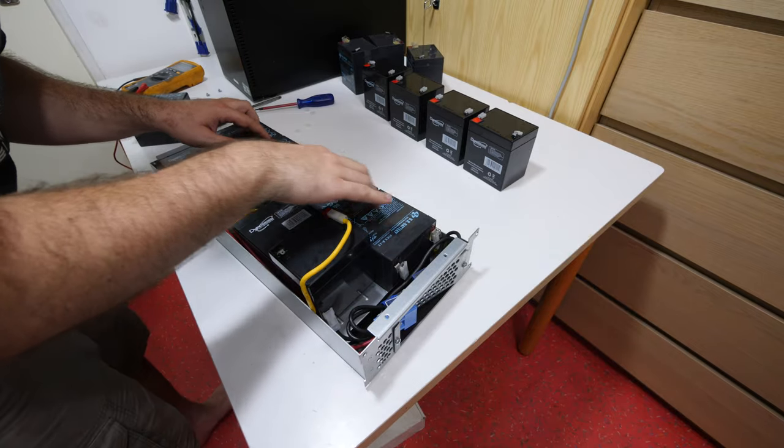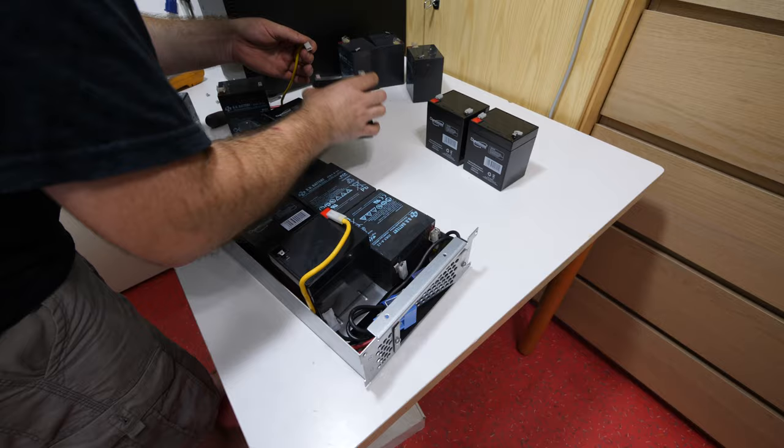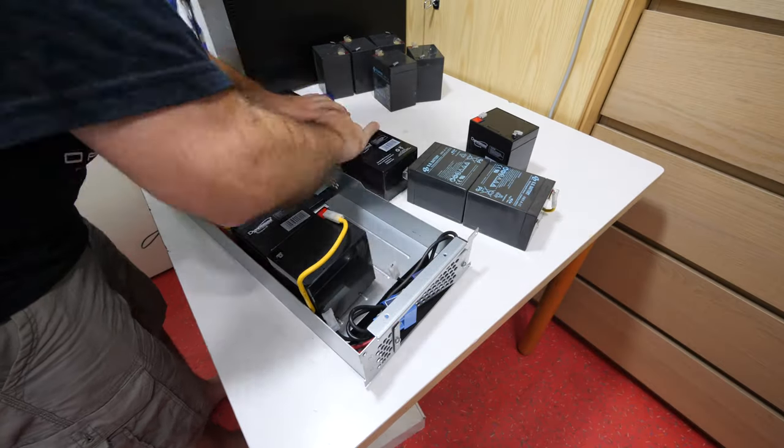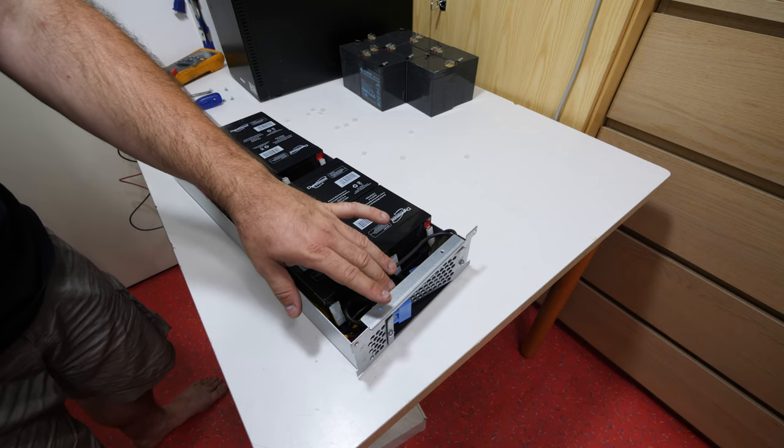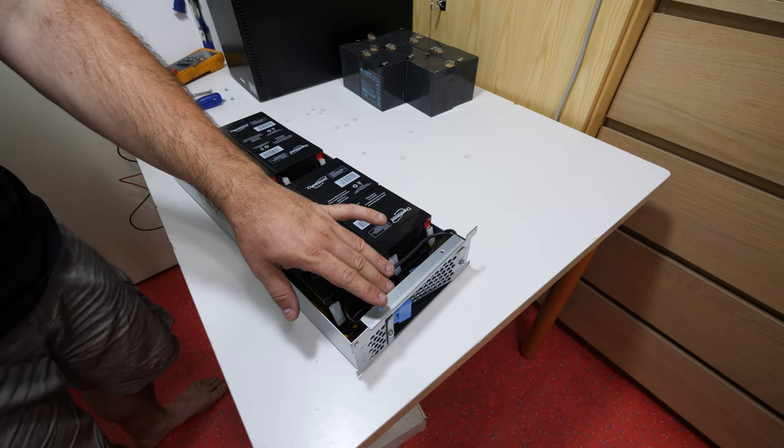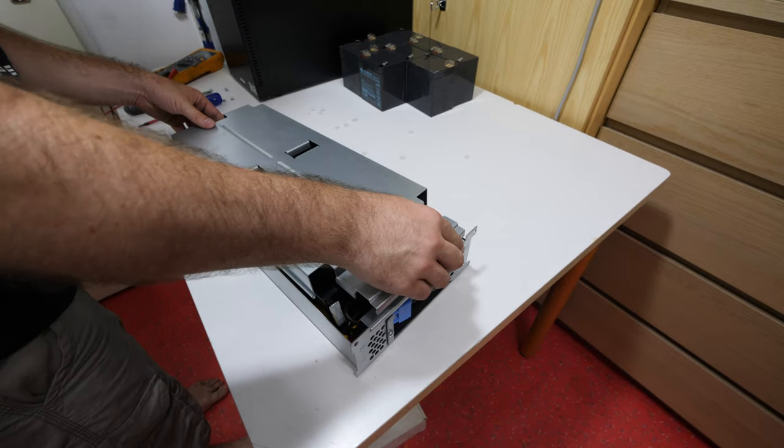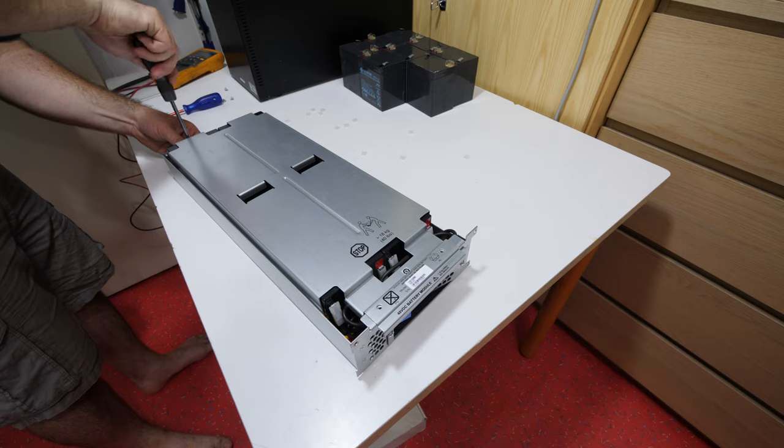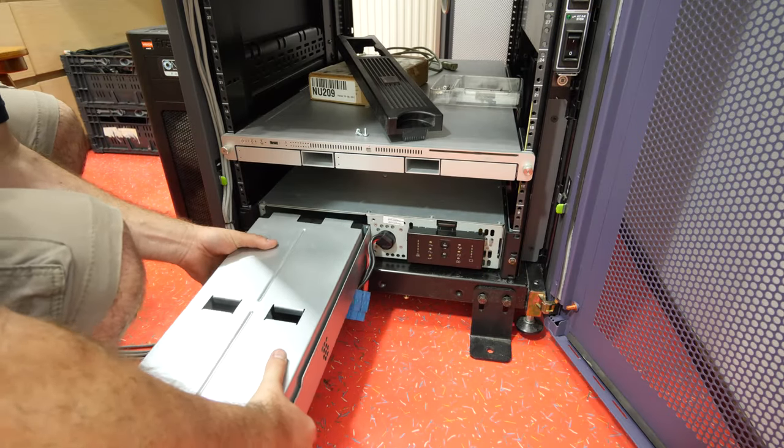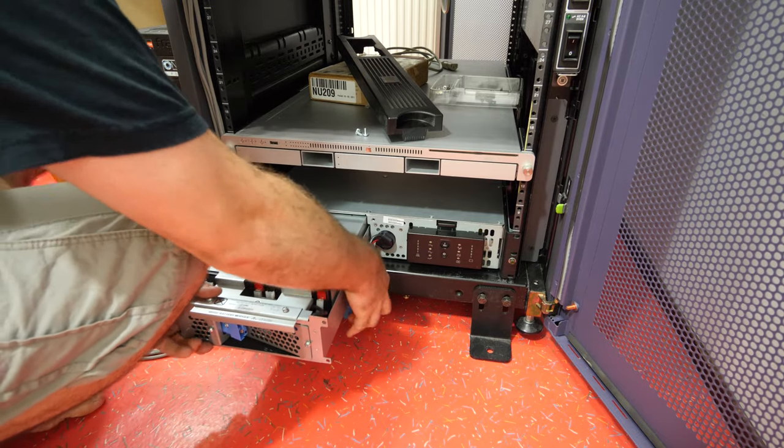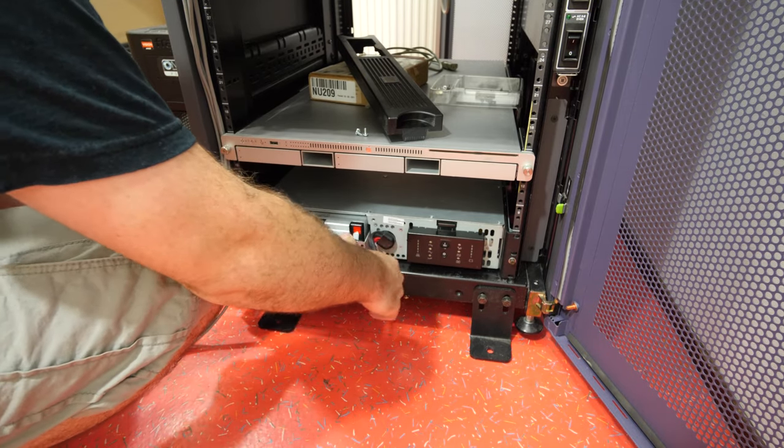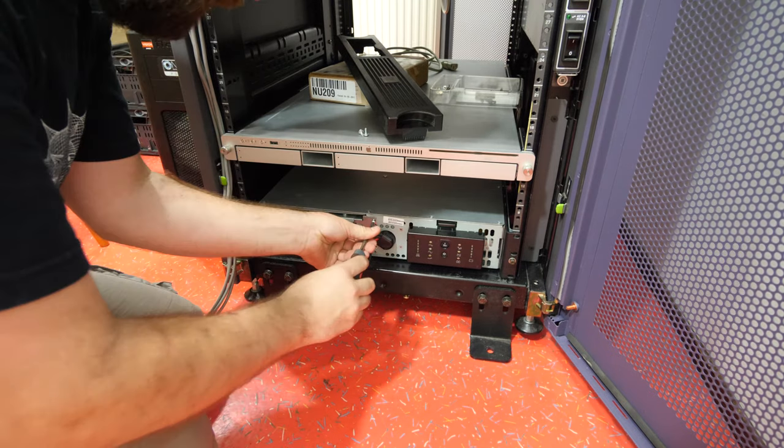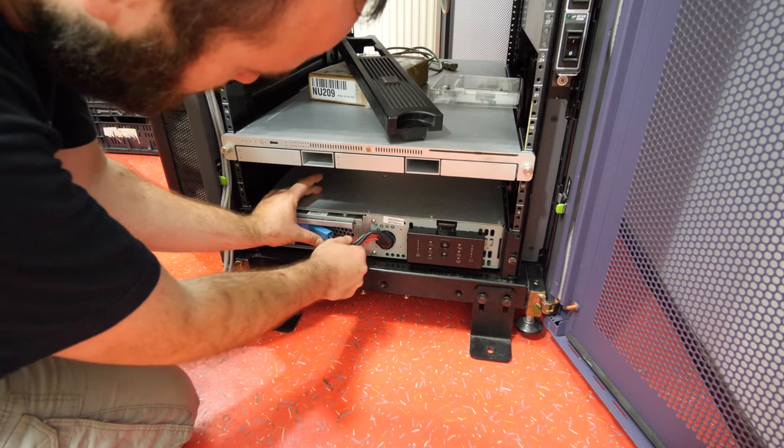Let's repeat it for the other side. Everything looks fine. I have 51 volt out of the connector, so that is correct. Let's install the top plate again and we can put it back in the UPS.